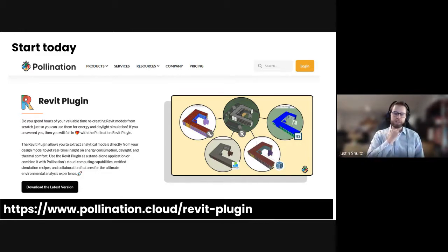I think one of the questions is, can we then bring that data back, which I know you mentioned, but I think we need better information around how an engineer would use this tool for load calculations, because a lot of people don't know that EnergyPlus is a totally sufficient calculation tool. People are just like, oh, it's not Trace 700 and it's not IES VE. It's like, IES VE is running the same ASHRAE heat balance engine. There's no difference. The difference is the report that you get, and people really like those reports because IES VE basically stole Trace 700's homework on the reports.